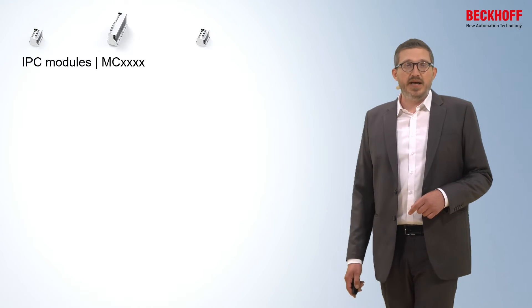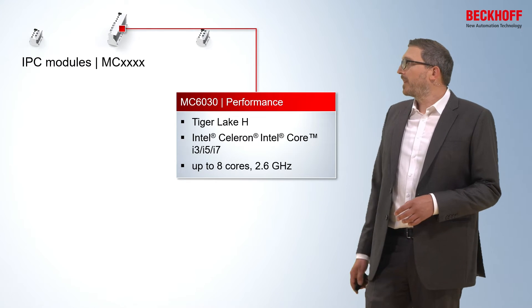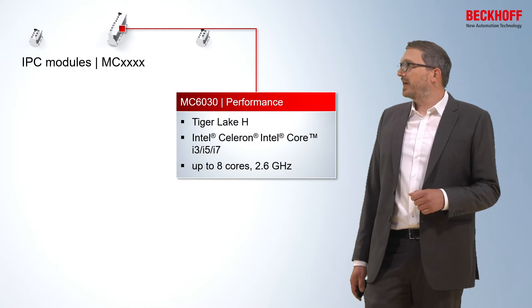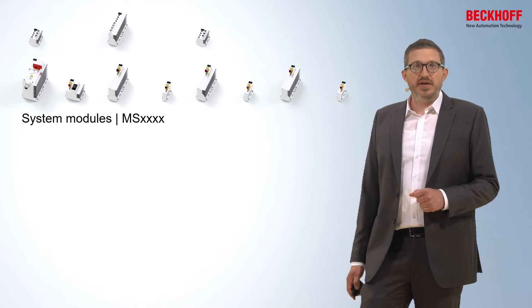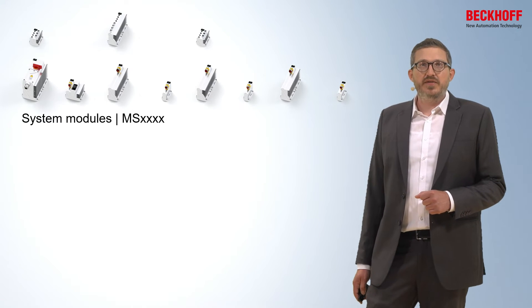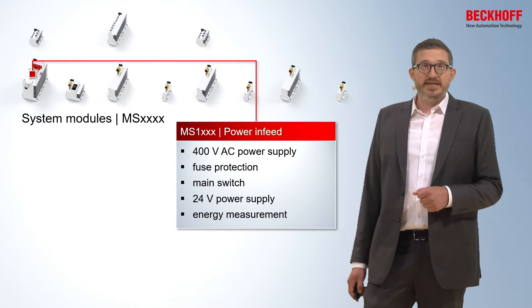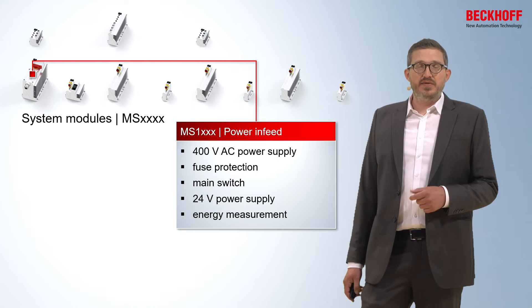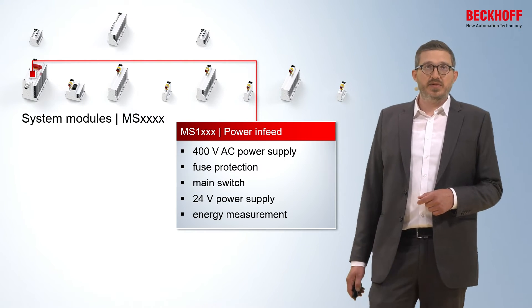The portfolio of functional modules is far larger — more than 100 modules or module varieties are available. Beginning with the IPC modules, you can find the well-known Beckhoff low-cost or high-performance IPCs. In the MC system as well, you can have your application running on up to 8 cores on an i7 processor. The next category is the system modules, where you find the main power infeed — you can supply all other modules with 400 volt AC. This module combines fuse protection, the main switch, a 24 volt power supply, and energy measurement components.